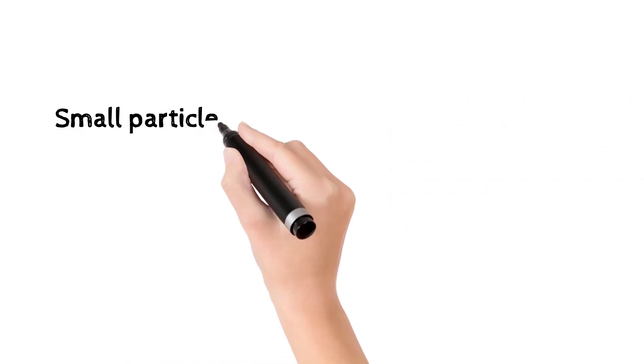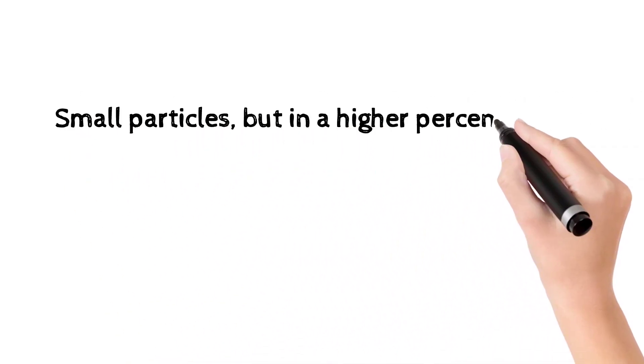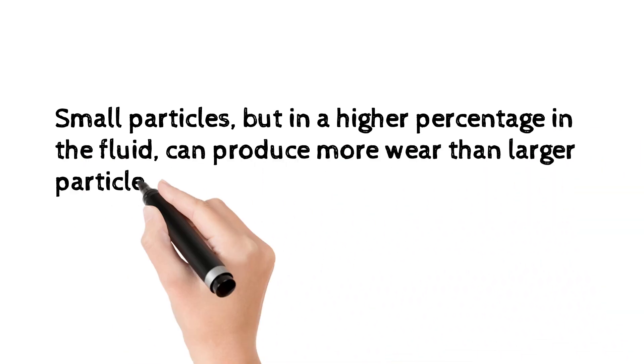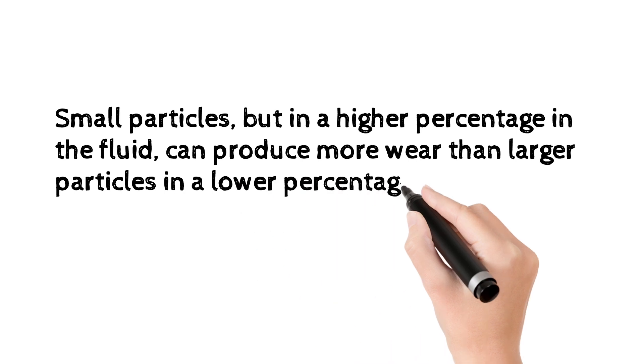Small particles, but in a higher percentage in the fluid, can produce more wear than larger particles in a lower percentage. Hard steels are recommended in the trim.